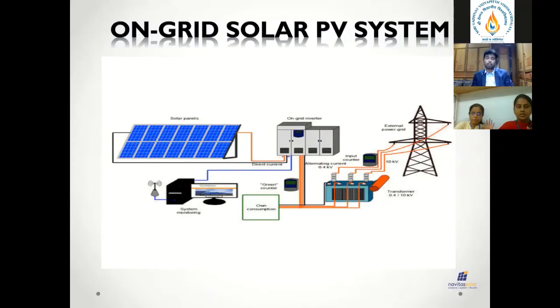Although the DC part remains the same across the industry, we connect DC solar modules in a series-parallel combination, generating current, voltage and so on. With the centralized on-grid inverter, we supply power to the inverter which converts DC into AC, then we step up the transformed power from 440 volts to 11 kV, 22 kV, or 33 kV, whichever is the nearest grid available for connection. This is the general functioning of the utility grid system, installed over acres of land.